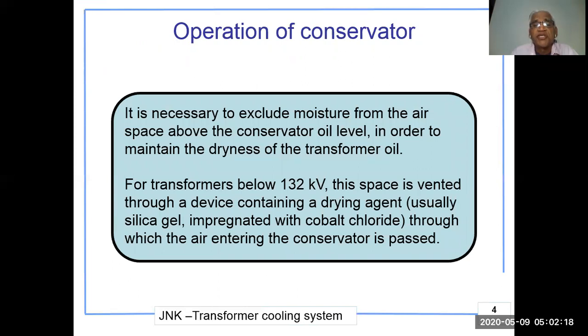For transformers below 132 kV, this space is vented through a device containing a drying agent — usually silica gel impregnated with cobalt chloride — through which the air entering the conservator is passed.